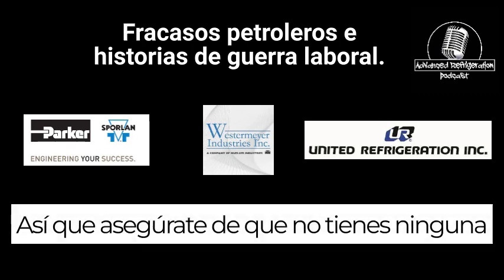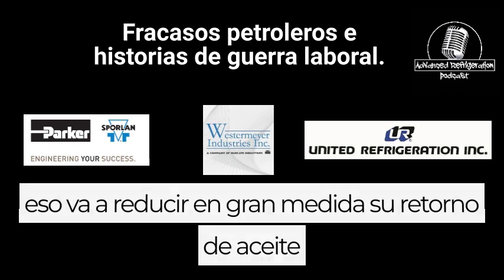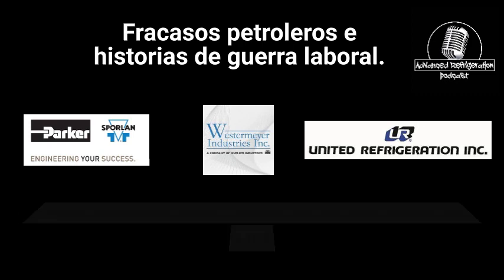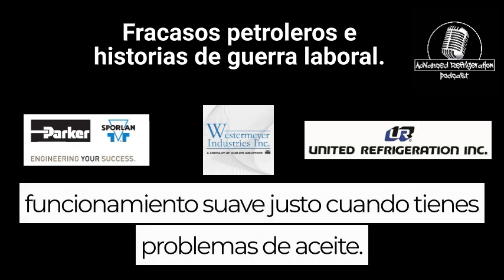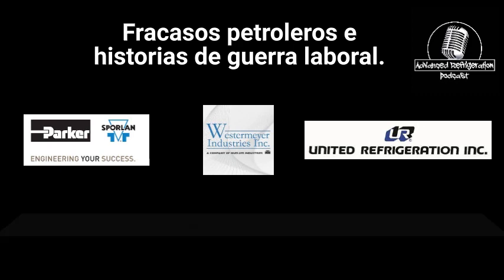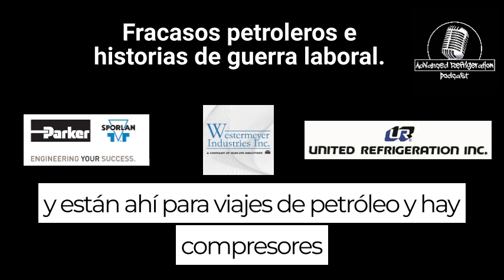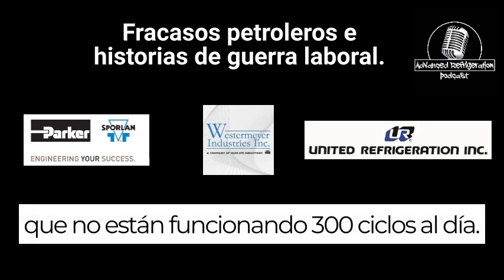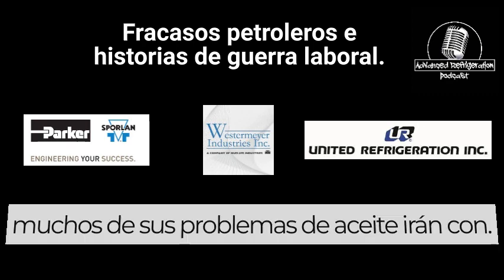So make sure that you don't have any restrictions on those suction filters, because if you do, that's going to greatly reduce your oil return to the compressors. So make sure that you have a smooth running rack when you have oil issues. I don't know how many times I've been behind guys who are there for oil trips, and there are compressors that are not running 300 cycles a day. So by the time you get that taken care of, a lot of your oil issues will go away.